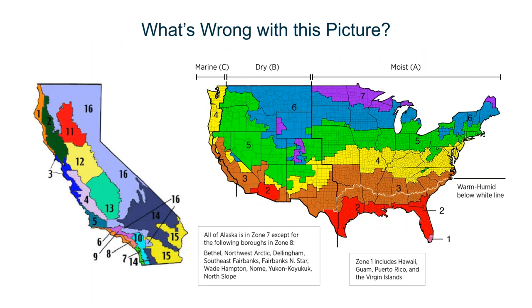How much insulation should we put in buildings? That depends on where you are in the country. What's interesting is to show side by side the codes driving the amount of insulation in our enclosures — the national IRC/IECC code map compared to the California map. There are seven climate zones for the contiguous 48 states, and 16 for just one state, California. California is renowned now for having a zero energy code. But the actual insulation requirements for California compared to the IECC really aren't that much more rigorous — in some cases, less.